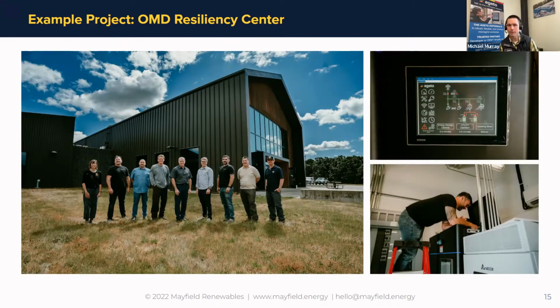One thing we can touch on here is there's been a few questions about the interconnect device for these systems, and you can see it in the small screenshot at the top. It's typically a utility grade protective relay for these C&I systems, measuring voltage and frequency on both sides of the contactor or motorized circuit breaker. If there's a fault on the grid, it'll isolate it. The microgrid controller gets feedback from that, and then we can black start the system in off-grid mode.